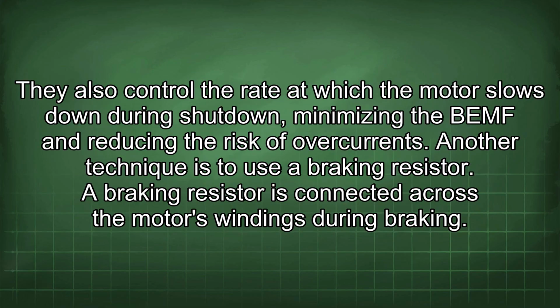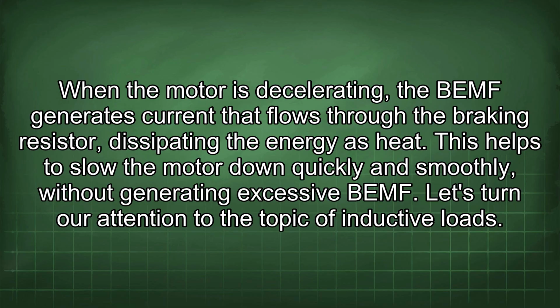They also control the rate at which the motor slows down during shutdown, minimizing the BEMF and reducing the risk of overcurrents. Another technique is to use a braking resistor. A braking resistor is connected across the motor's windings during braking. When the motor is decelerating, the BEMF generates current that flows through the braking resistor, dissipating the energy as heat. This helps to slow the motor down quickly and smoothly without generating excessive BEMF.